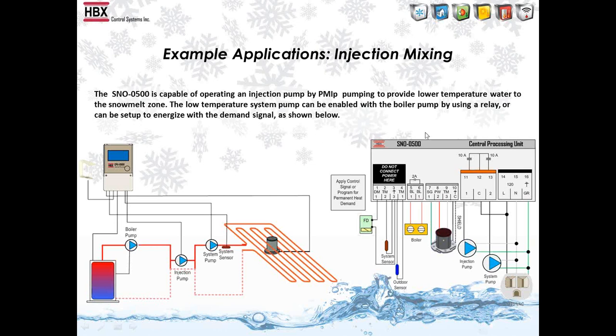A couple example applications. So injection mixing, like I said. So the boiler pump is connected to the boiler. We would run the injection pump and the system pump. The system sensor would be attached somewhere before, not on the return line, but on the outgoing side. So as you can see here, we've got a little forced melt demand. We have the system sensor and the outdoor sensor. This connector would go to our boiler. We have our snow sensor, so we can see the injection pump, the system pump, and then basically we have the 110 going into it as well.